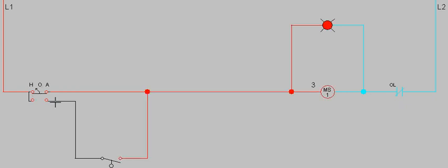Now, as we've brought up before, let's say there were some debris caught in the pump impeller and the current were to go up, then our overloads would trip and turn off the motor. So that's the purpose of the overloads in the circuit: once the current rises higher than the setting on the overloads, we will lose power to the pump. Once that's cleared, we can reset; hitting the reset button on the overloads resets that to the closed status and allows it to run.